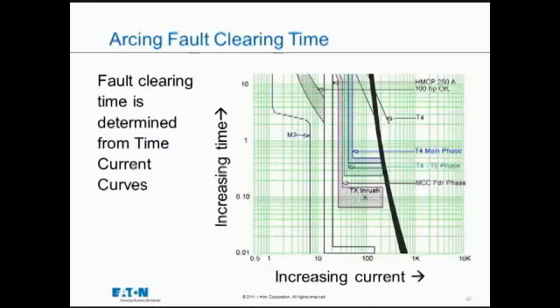And once we know arcing current, we can determine our protective device clearing time. And we use graphs called time current graphs from a coordination study. And you have to certainly have some idea of how these graphs work and why they're used, but that's the connection. We find arcing current, and then we go to our protection settings, our time current graph to determine the exposure time.